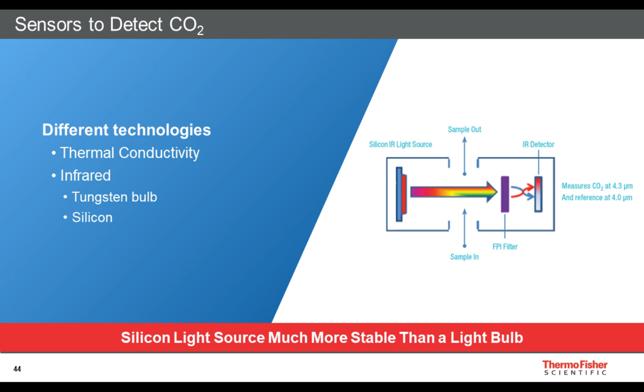Now, the thing about a tungsten infrared bulb is that the tungsten filament degrades over time as it's heated, and because of that, the light intensity decreases over time as well. When the light intensity decreases, that contributes to decreased accuracy of the measurement and drift of that measurement. So one of the options is to get a newer technology where, instead of using tungsten, a silicon light source is used to provide that light. And this turns out to be much more stable and much more long-lived than tungsten bulbs. It's kind of the equivalent of moving from an incandescent light bulb to an LED light bulb. And so as I said, a silicon light source is much more stable and long-lived than an older tungsten-style infrared light bulb.